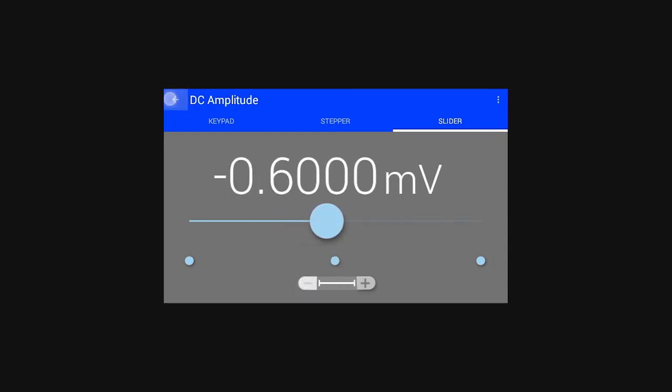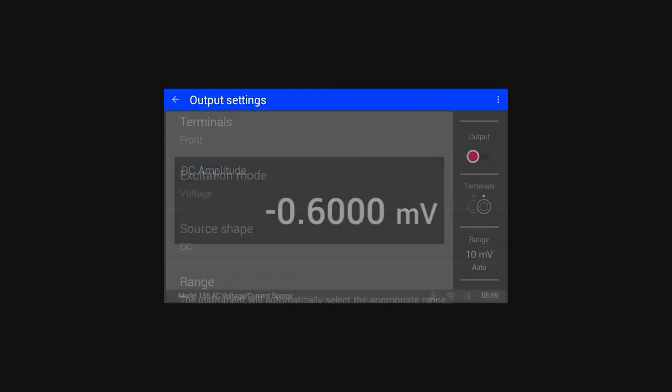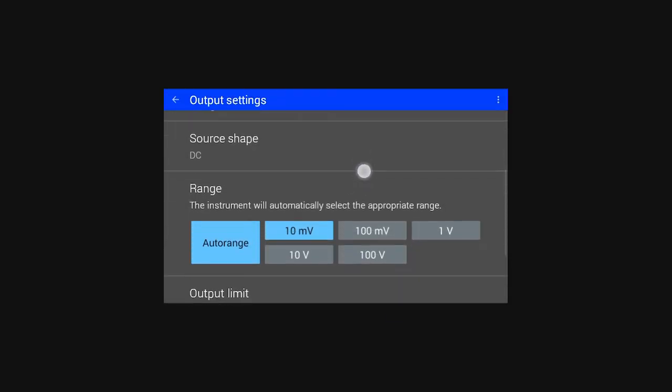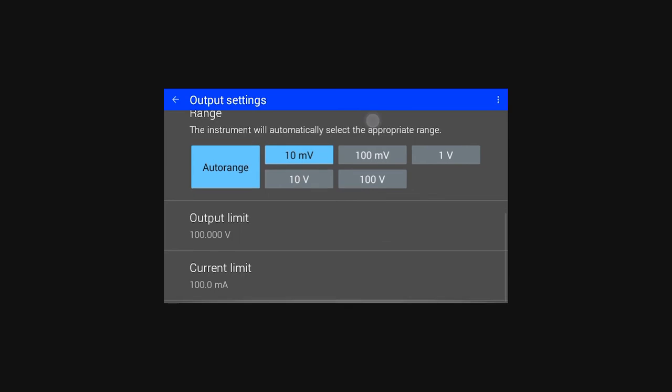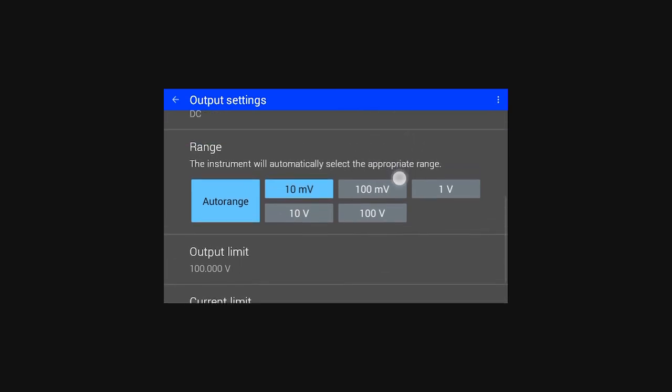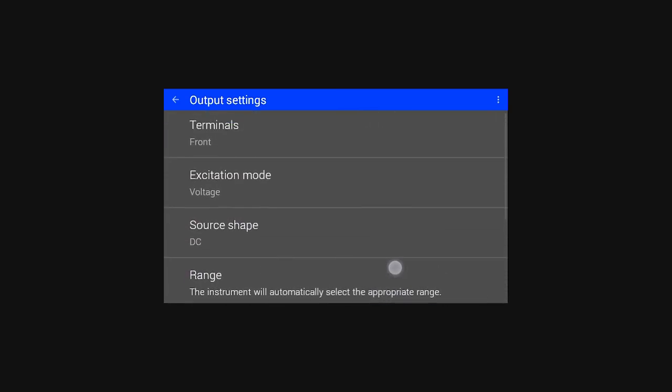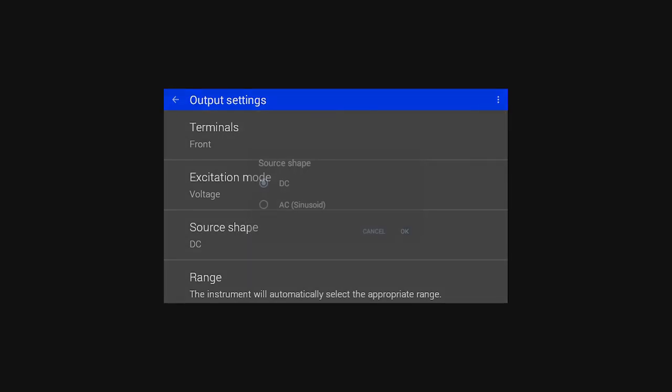Heading back out to the home screen, we'll change the mode from DC to AC. To do so, tap on the menu icon in the top left. Of the options presented, tap on output settings, and seen here are options that change characteristics of the output. Now we'll tap on source shape and change the mode from DC to AC or sinusoidal.